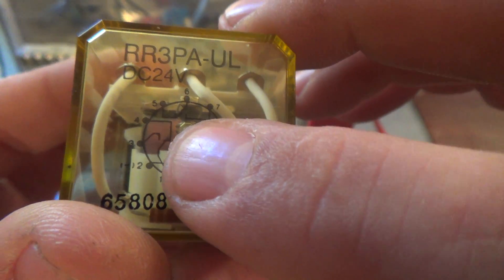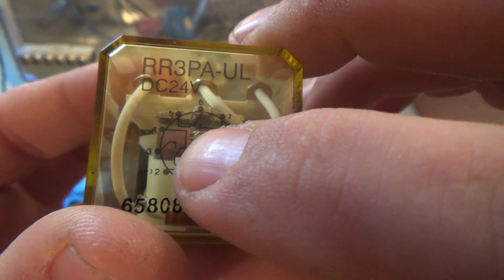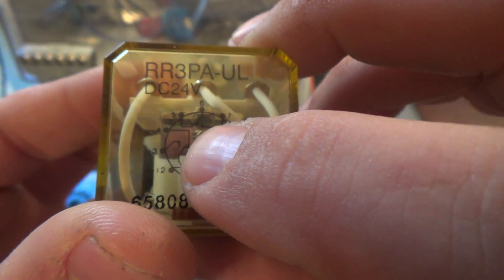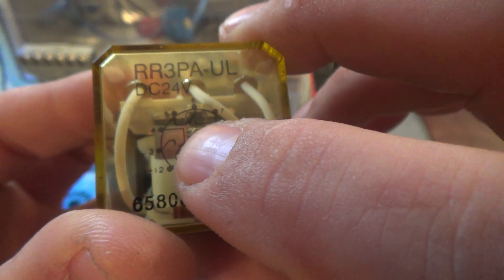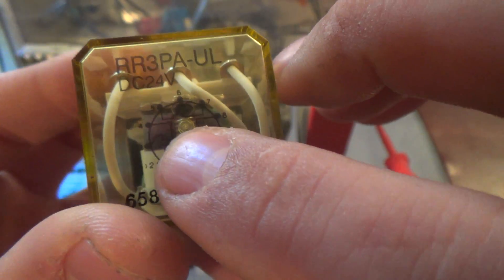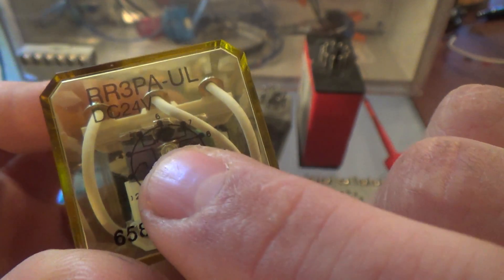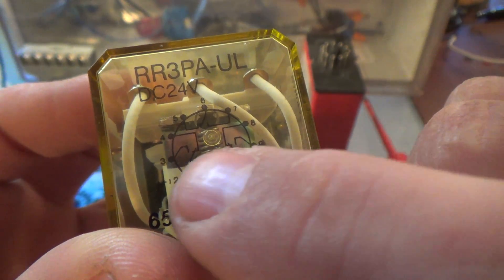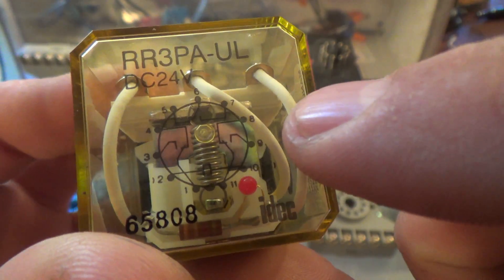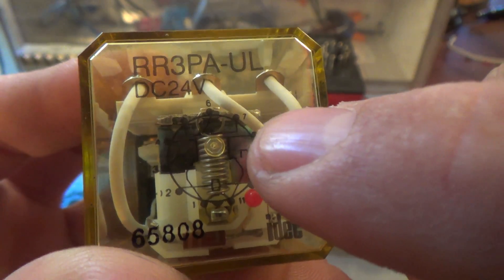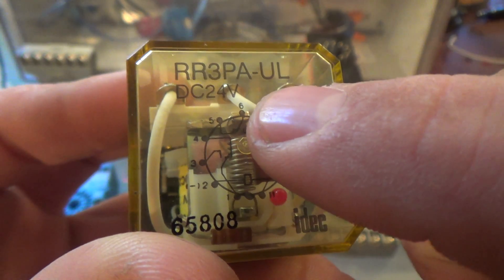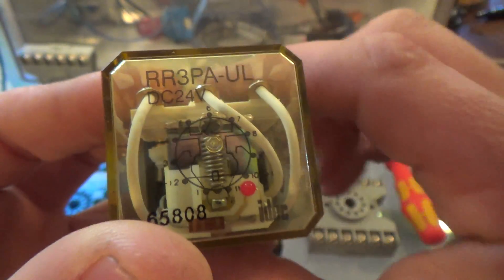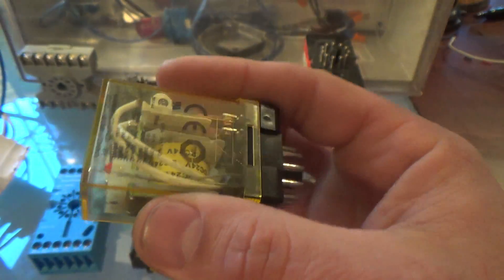Also you have pin one down here, terminal one, and it is going up and normally closed with pin four. When you apply power to the coil, energize the coil, that will change and pin one will disconnect from four and connect to three. So it's normally closed with four but it would change state and be normally open and then also change state with three and close. That's going to be true with all three sets of contacts that are on here - one, two, three, and you got your coil at the bottom.